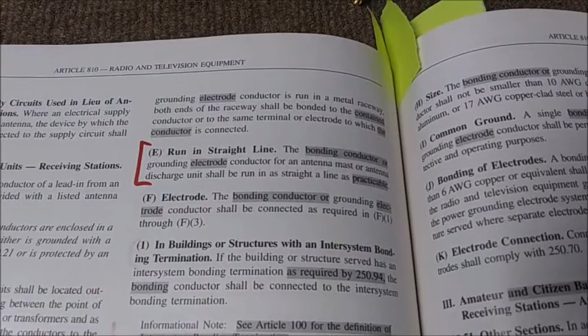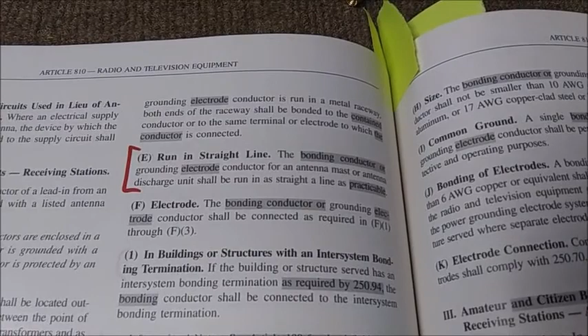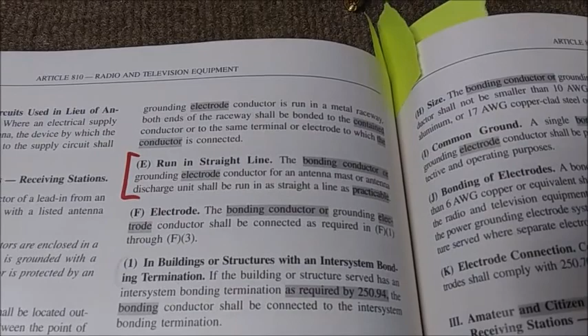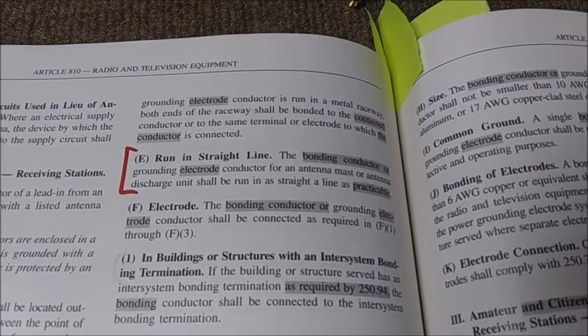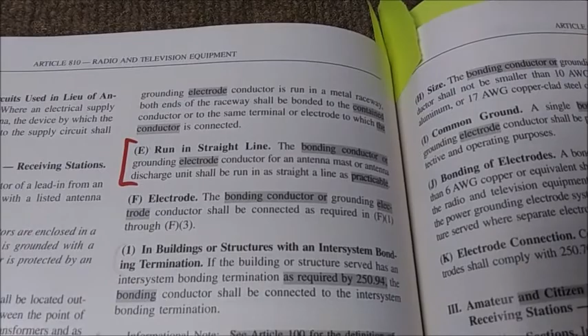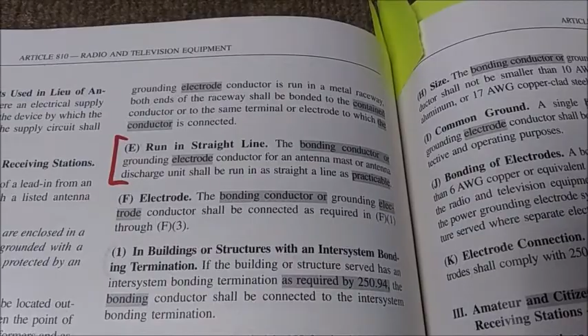I straightened the ground wire from the top at the weatherhead all the way down. Installed a commercial bonding clamp on the conduit after scraping the paint off the conduit. Cleaned the ground wire. Ran it with a very smooth 3-foot radius to the ground rod. And happened to call the electrical utility a while later to do a disconnect so I could work above the lines. And they looked at that and they said, whoever installed that ground knows the code. And I said, thank you, I did that.